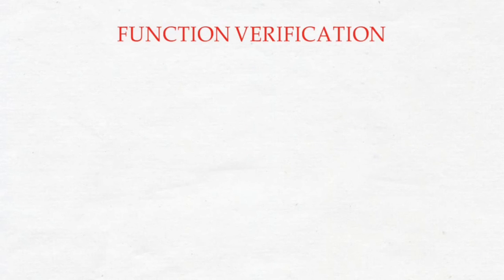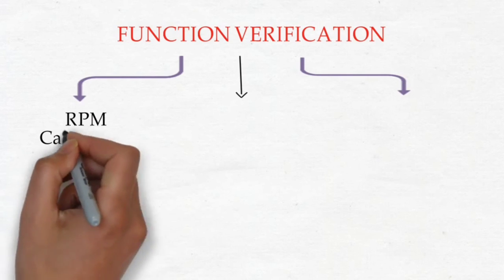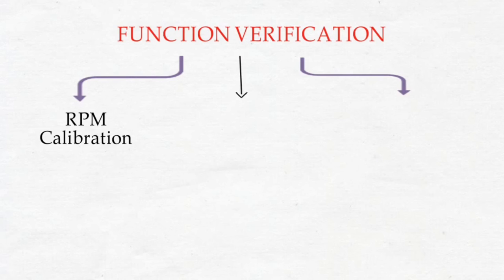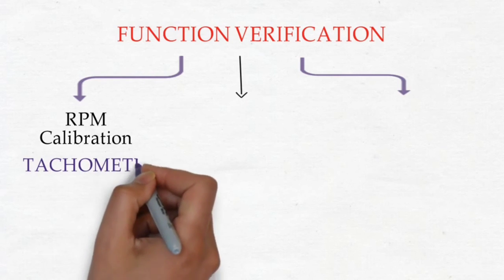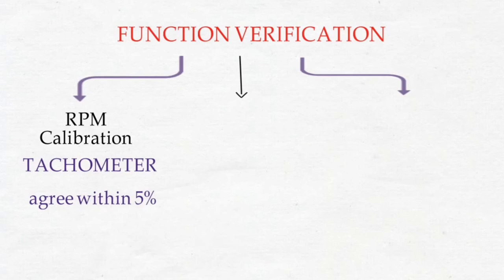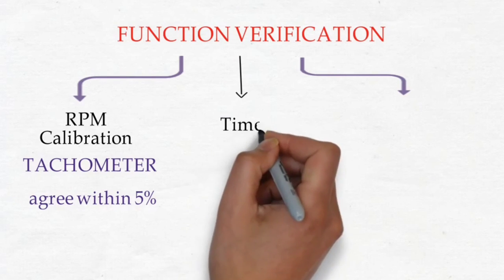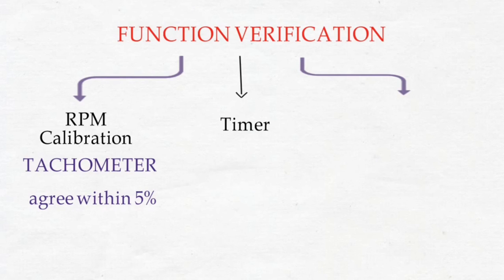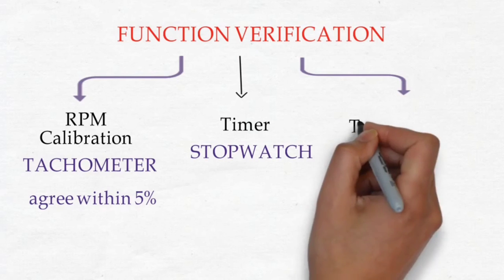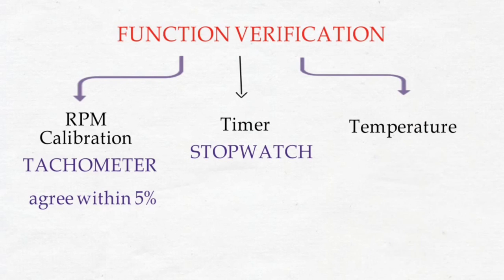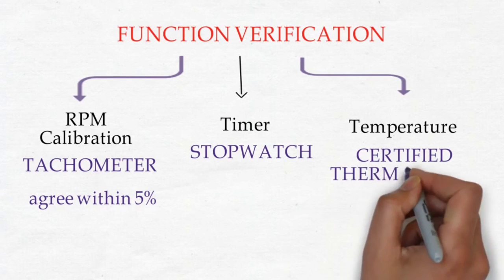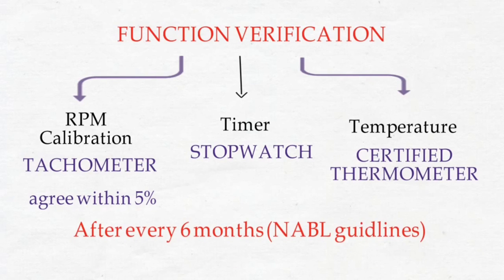For function verification: first, RPM calibration — the speed should be checked using an external tachometer, and values should agree within 5% of the built-in tachometer. Second, timer — timing intervals should be checked using a stopwatch. Third, temperature — for refrigerated centrifuges, the chamber temperature should be verified against a certified thermometer. All these functions should be verified every 6 months according to NABL guidelines.